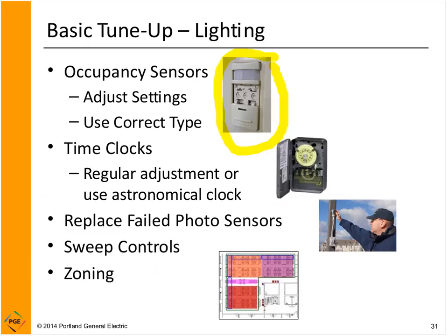A lot of times in existing buildings, these sensors are going to be placed where an existing light switch is. But if you're in a conference room, for example, that light switch may be behind a door, and the occupancy sensor may not be able to do its job. It may not be able to detect motion and react appropriately by turning on or off lights. So one thing to think about is maybe a wall sensor is not for me, but a ceiling mounted sensor is a good application.